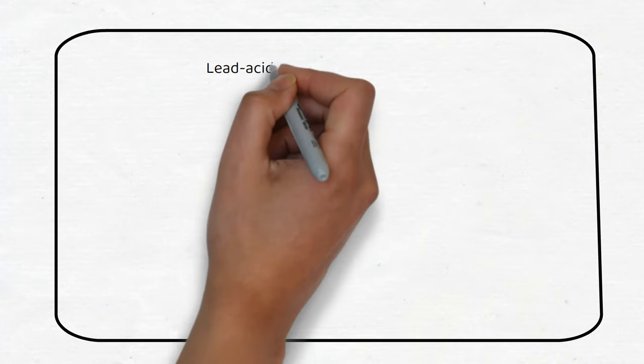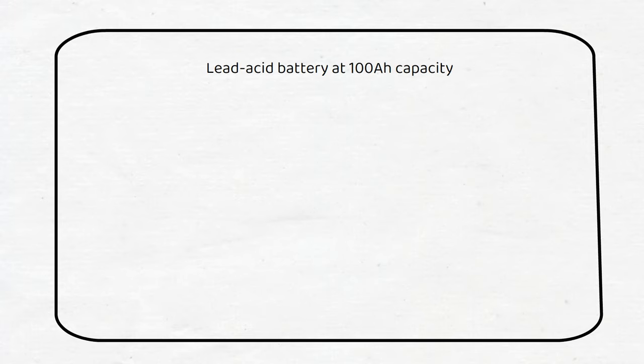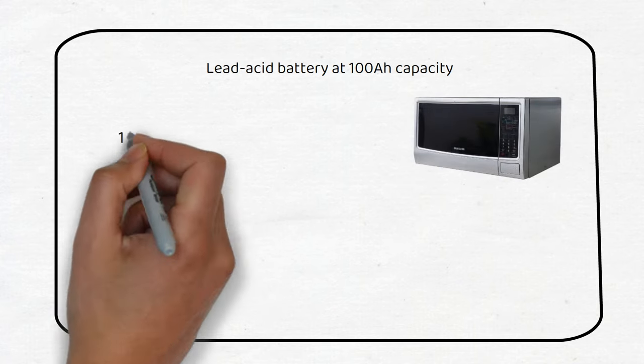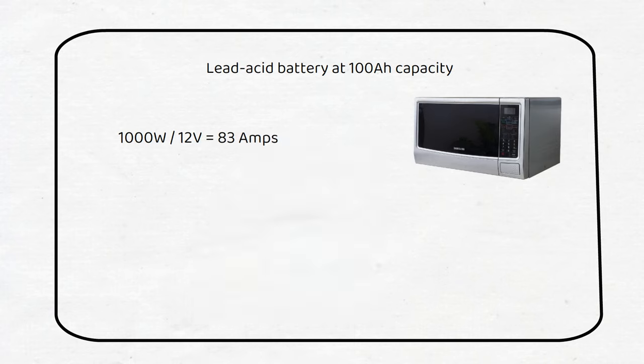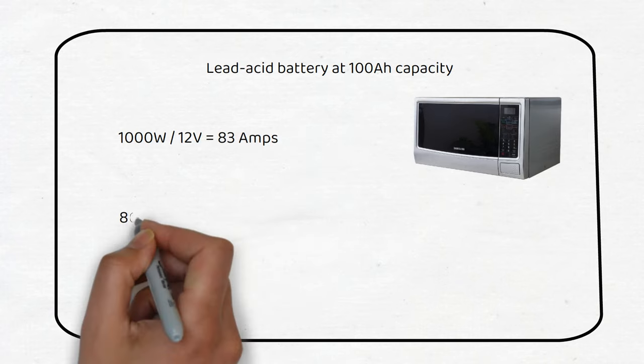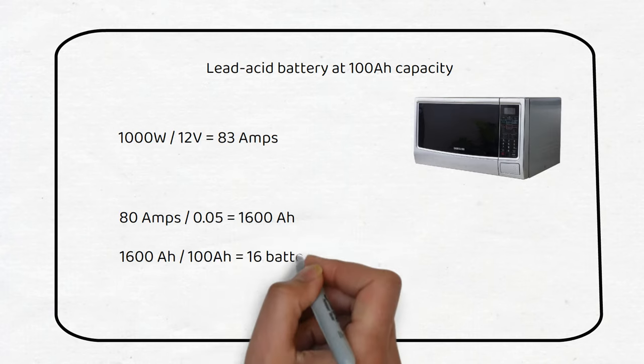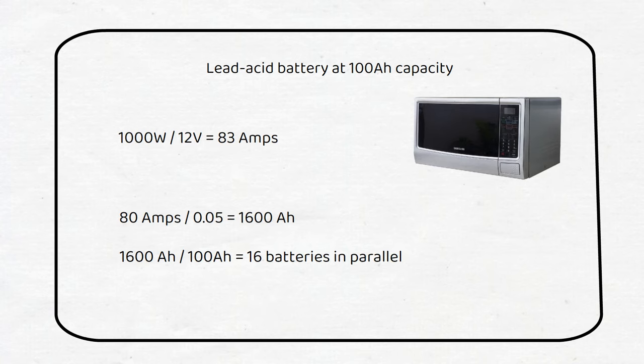If we have a lead acid battery of 100 amp hours, we can use the rated capacity at 0.05C or C20. So if we were to power a 1000 watt appliance through an inverter, we could draw 83 amps at 12 volts. Using the formula, we can see that we need 16 batteries to supply this 83 amps of current to achieve the rated battery capacity. Of course, we can use fewer batteries, but then the discharge current of each battery is higher.